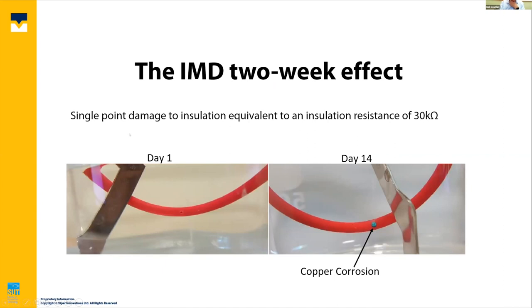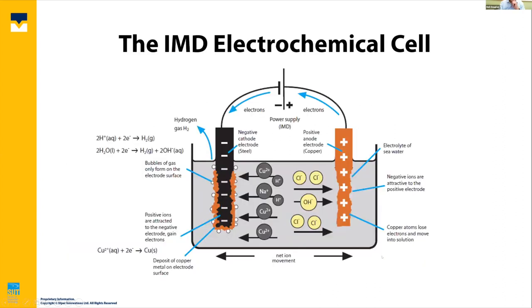After just 2 weeks, we took that cable out of the seawater, and you can see some copper corrosion on the surface of the wire. And this was with an insulation resistance of 30 kilo ohms. So we made a scientific hole using a pin in the material. We measured the insulation resistance, it was 30 kilo ohms. And after just 2 weeks of energizing that cable, or monitoring that cable, I should say, with the line insulation monitoring device, we ended up with copper corrosion. Now, it's not surprising.